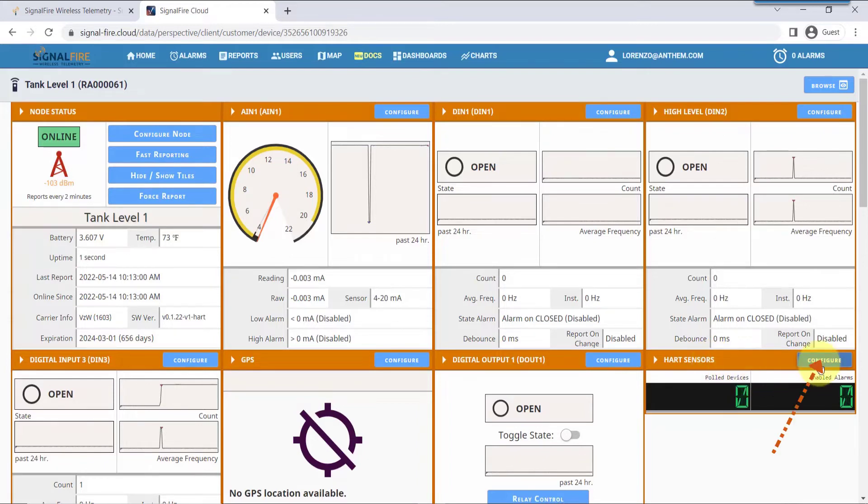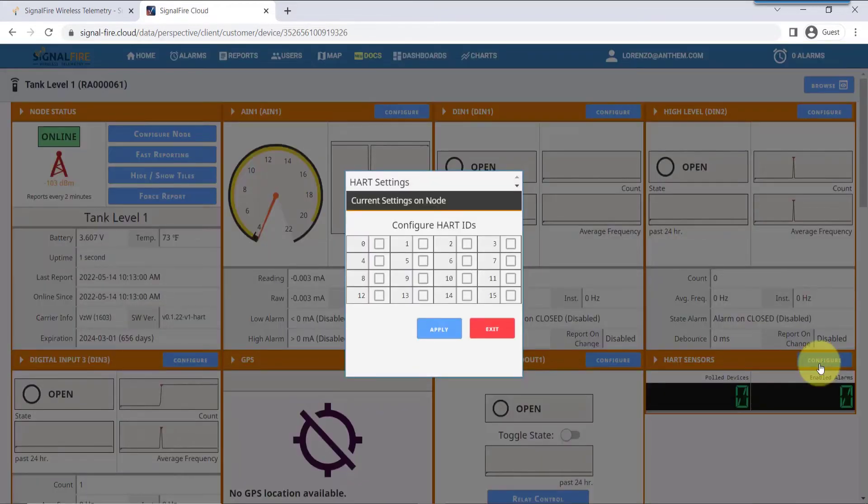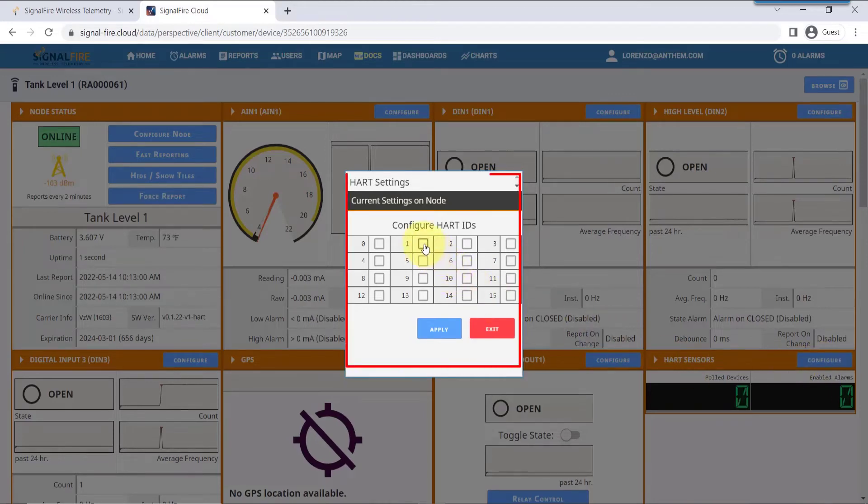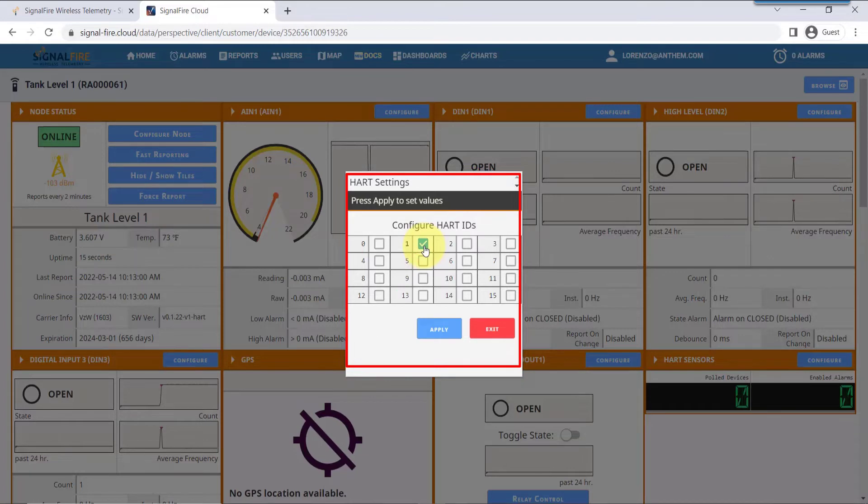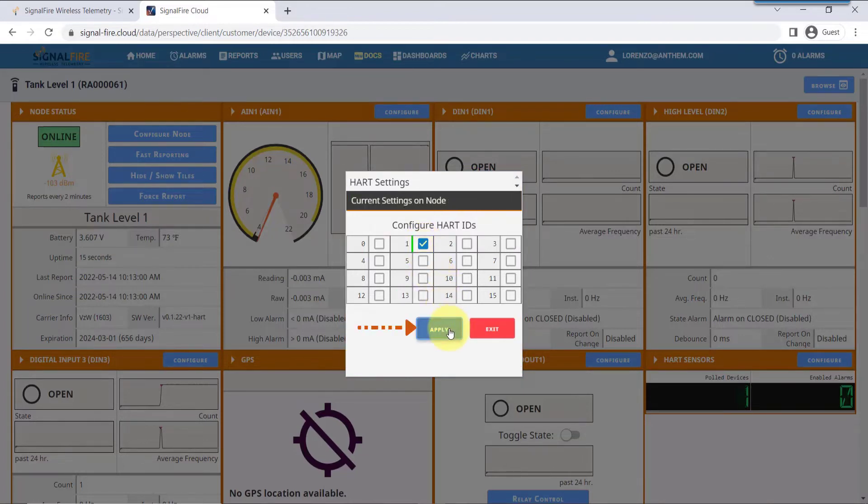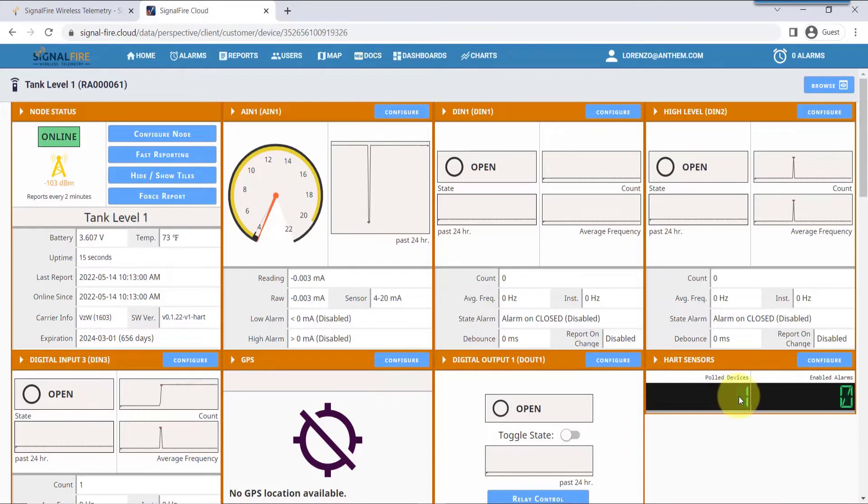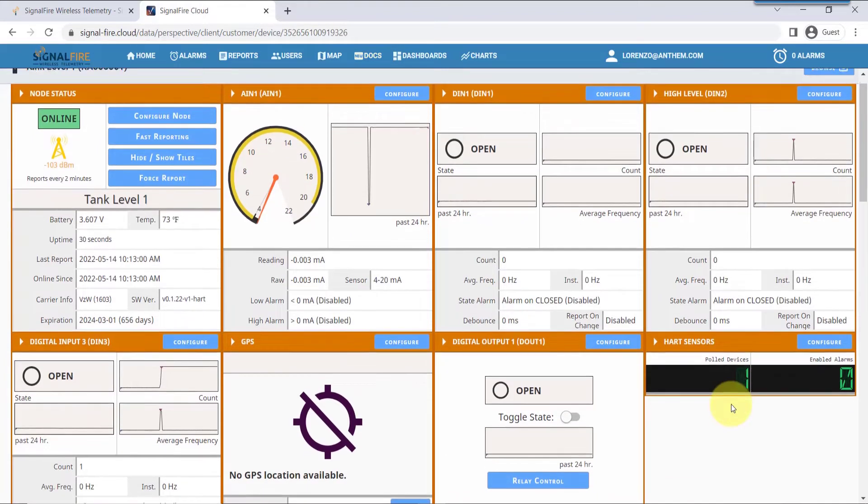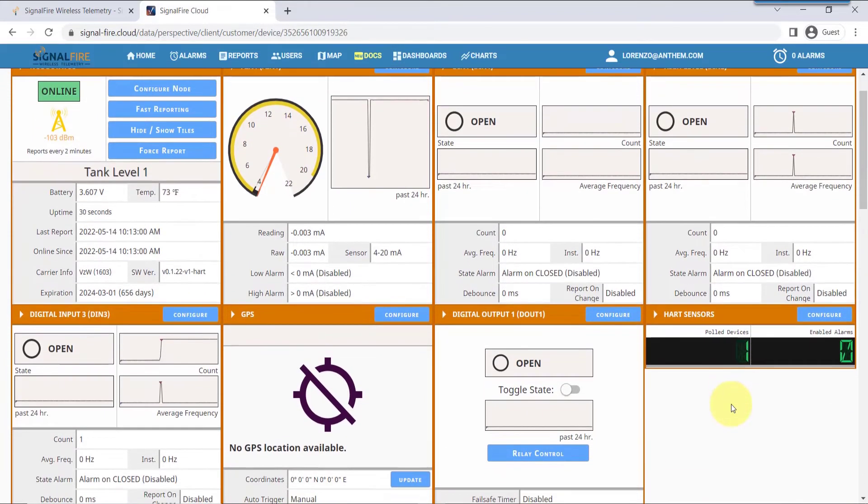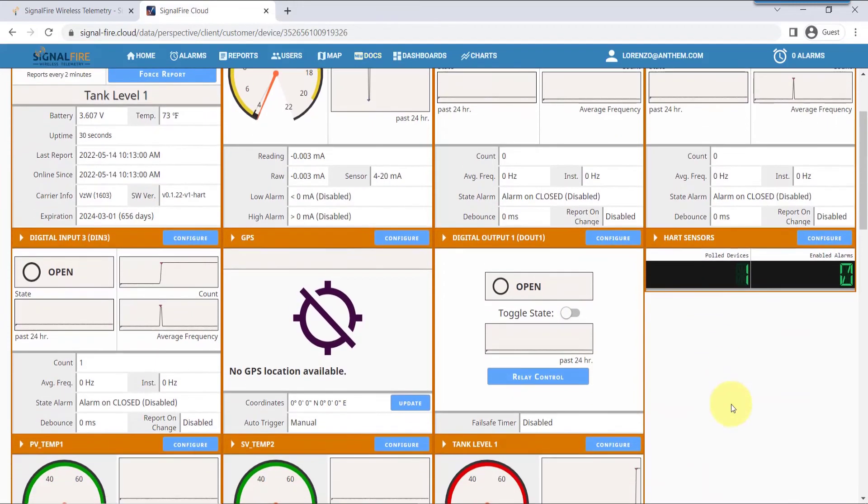Now let's interface the Ranger with the HART device. Click on the Configure node on the HART tile and then activate the HART ID associated with your HART instrument. Hit apply. When the change has been accepted, it turns to green. The tile now shows that you have one HART device being polled by the Ranger.